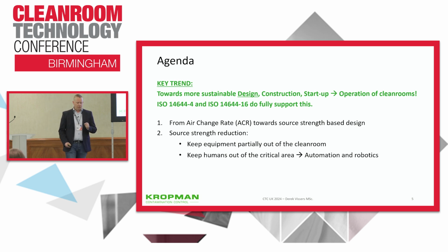I have two topics. The first one is from air change rate based design towards source strength particle emission based design. And the second one is how can we reduce the source strength in our clean rooms. We can do that by keeping equipment partially out of the clean room and also by keeping humans out of the critical area. There we see more and more automated processes and also robotics. And I will show you some practical examples about source strength reduction.